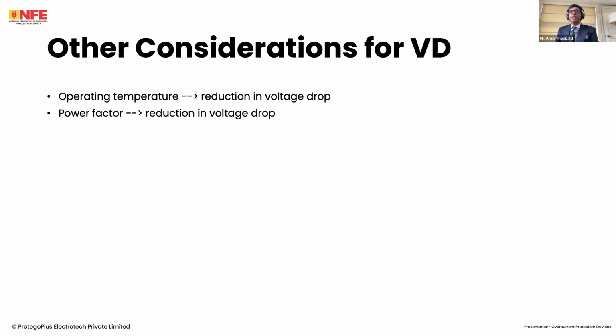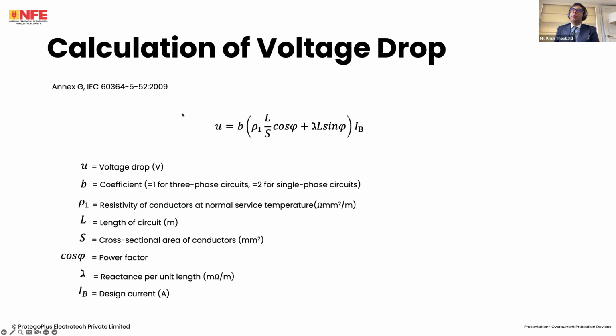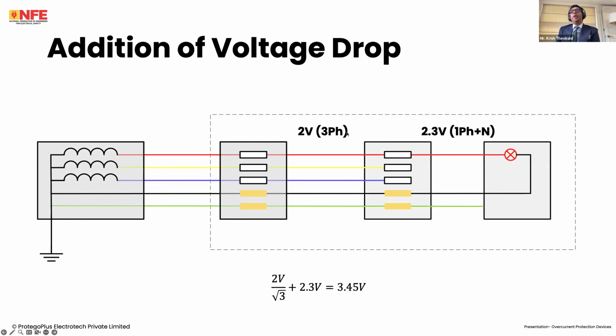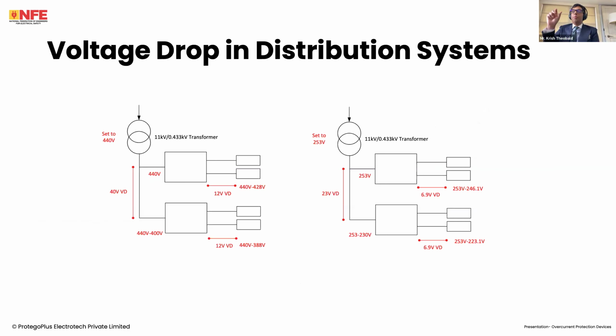Now, other considerations. If you have an operating temperature where the cables are not being run at the full current carrying capacity, you can get away with a slightly lower voltage drop. And of course, power factor. Like I mentioned here, you have to take into account power factor anyway. And manufacturer data will also do that. You have to apply a correction factor.